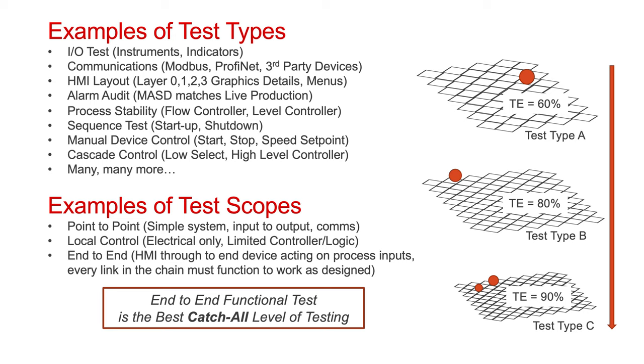In automation systems, for example, certain test types we may have include I/O testing of instruments and indicators — just testing that the inputs and outputs are reading correctly in the controller. Beyond that, we also have high-level communications buses, for example Modbus and ProfiNet, for third-party devices. HMI layouts, whether that's layer 0, 1, 2, or 3, HMI graphic details, and menu systems. Alarm audits against a master alarm and setpoint database, making sure that matches live production, is another form of test.